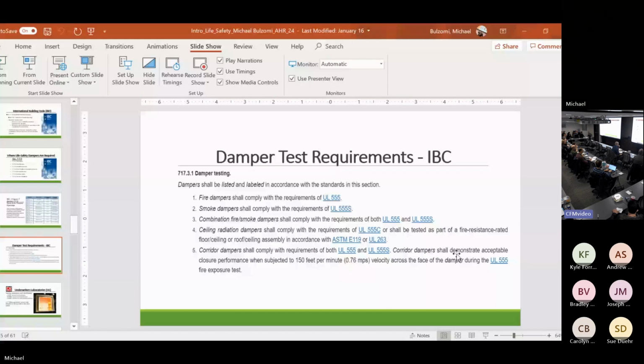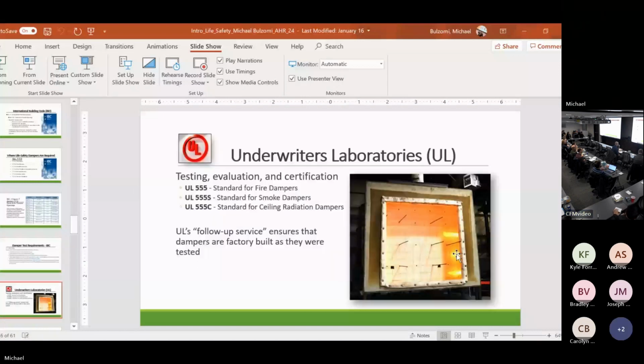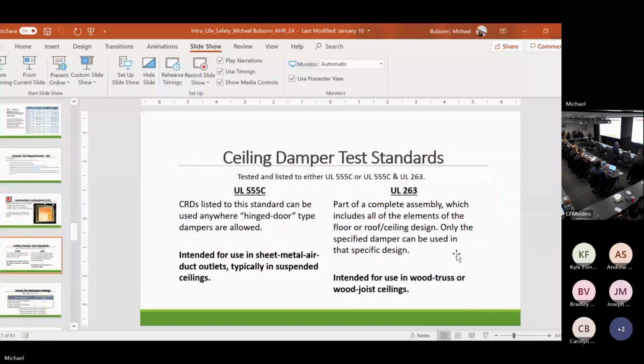Damper test requirements. I'm not going to go through all this. For those of you doing commissioning, actually, no, this is where it states here in the building code. It's chapter 7, 717.3.1. Fire damper shall comply with the requirements of UL 555. Again, nothing says fire dampers shall be UL labeled and listed. So we go back to those ceiling dampers, test standards. There's two different test standards for ceiling dampers.